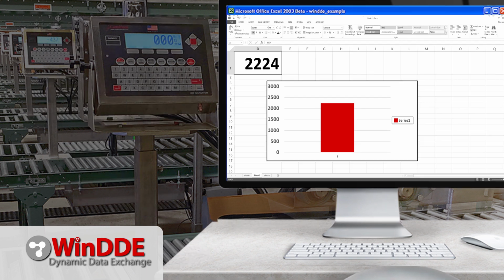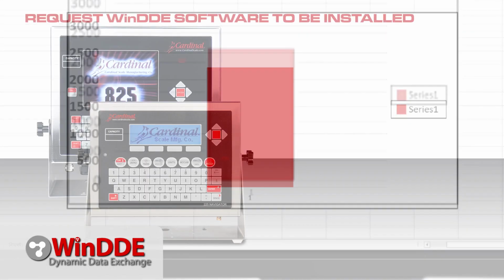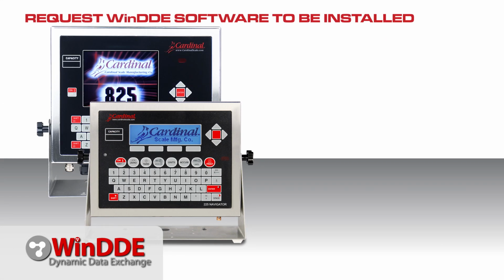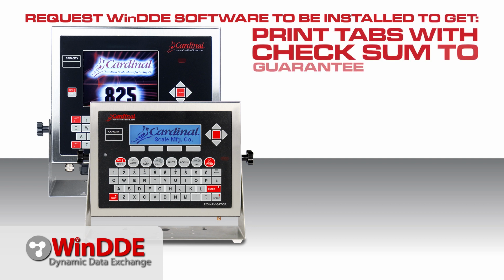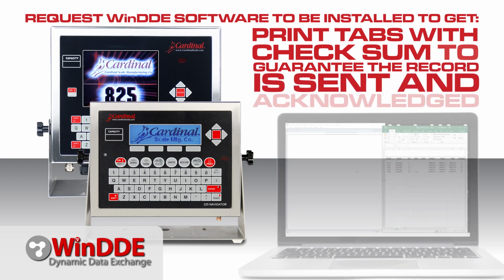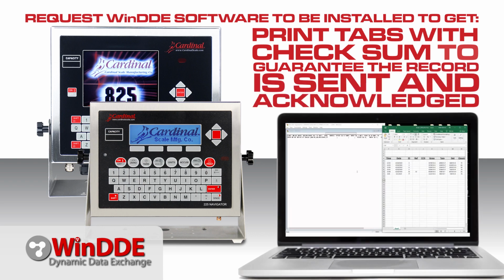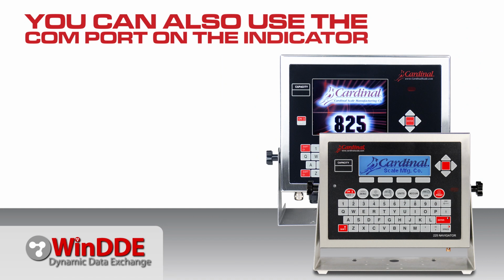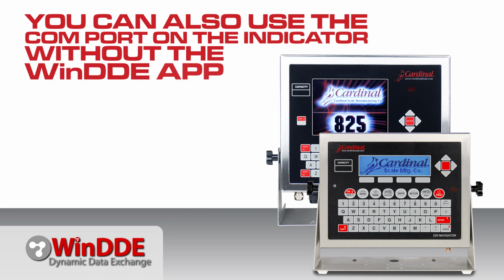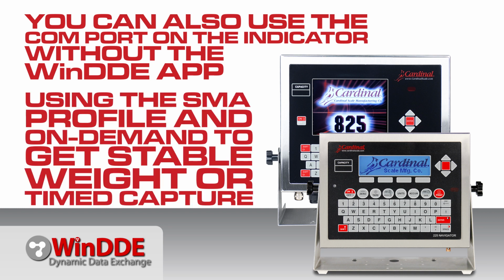Typically, you would want to request the WinDDE application to be loaded on the 200 series or 825 indicators in order to get the print tabs with a checksum to guarantee that the record is sent and then acknowledged. This is the preferred method. You can also use the COM port on the indicator as normal without the WinDDE app loaded with the SMA profile and on demand to get stable weight capture or timed capture.